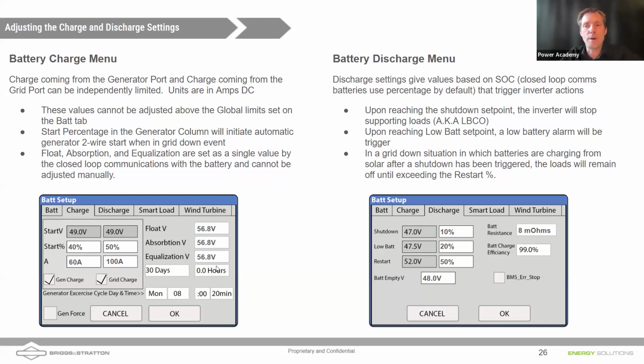The communicating battery will set this automatically itself. If we're not using a communicating battery, these values would be different. The float, we would use 54 volts. The absorption, we would use 56. And equalization, we would use 56, but 0 hours of time to disable equalization. That's a lead acid feature.